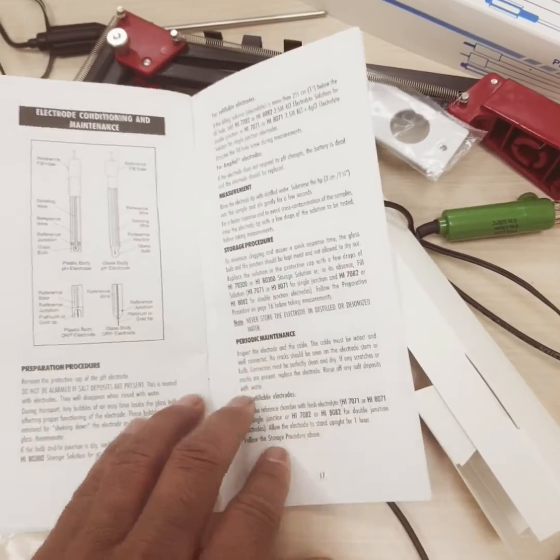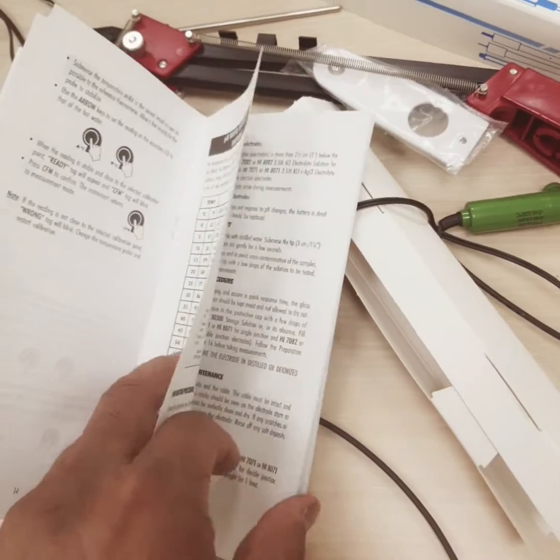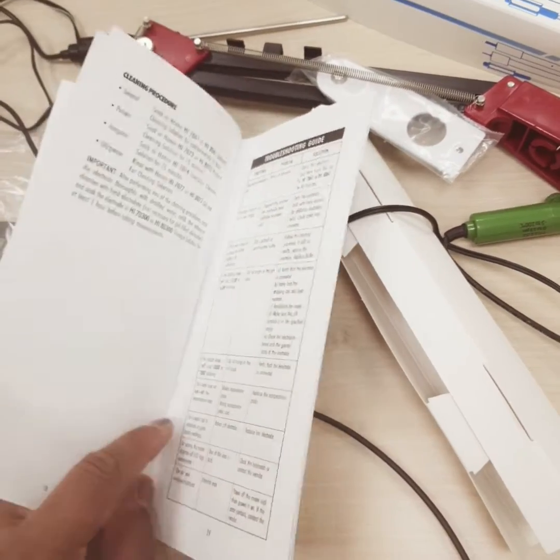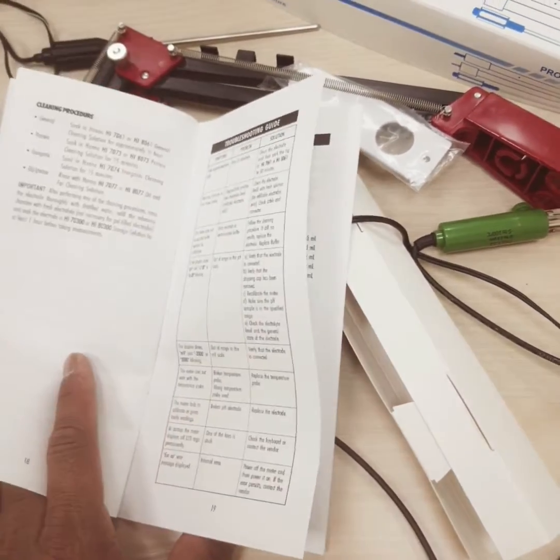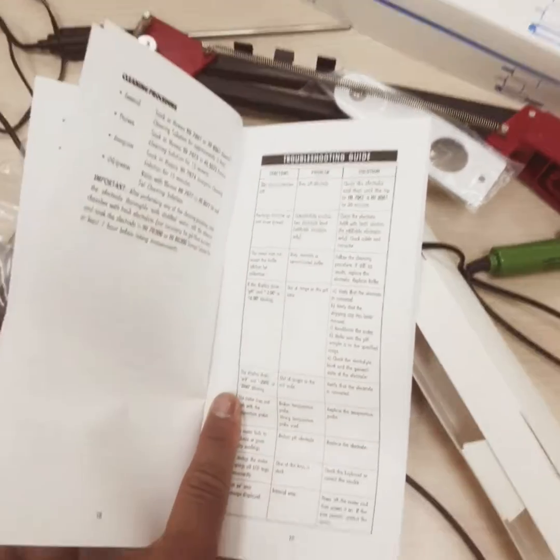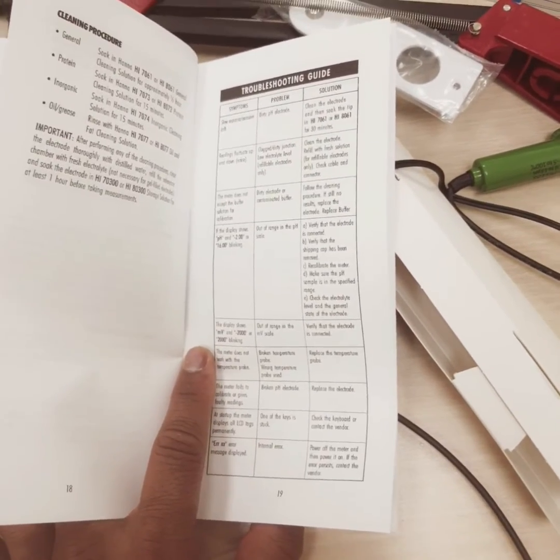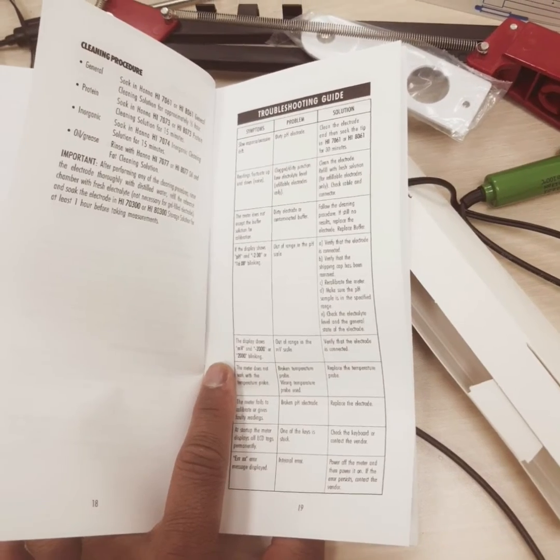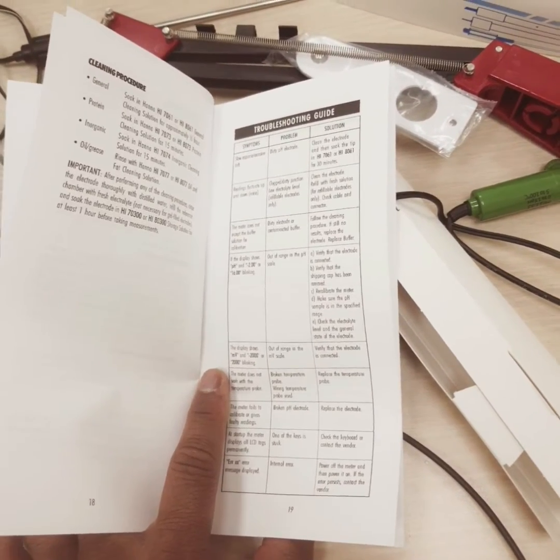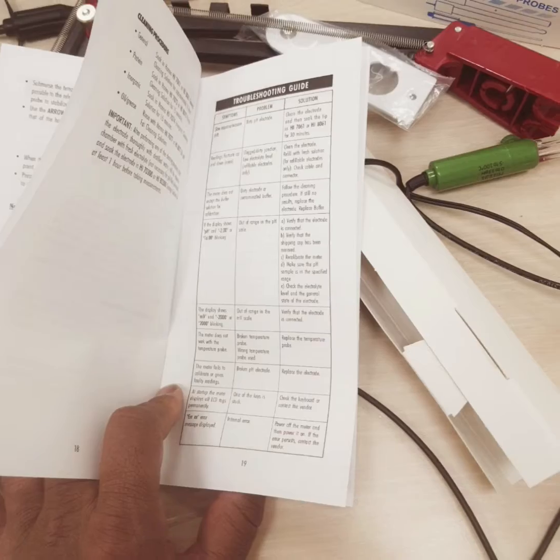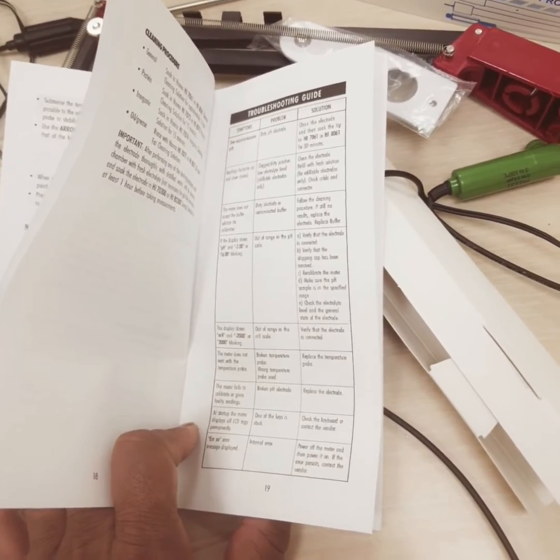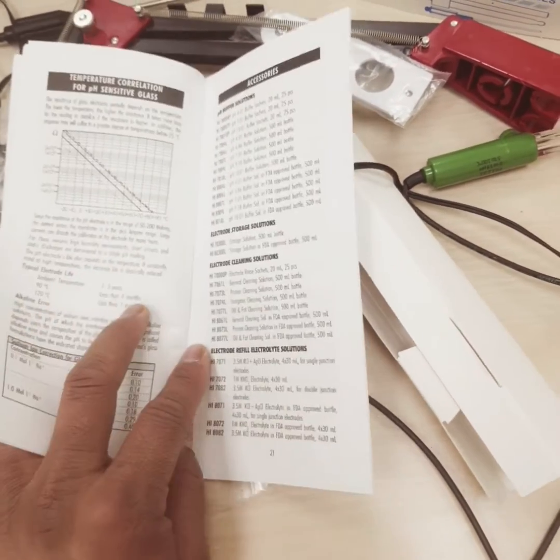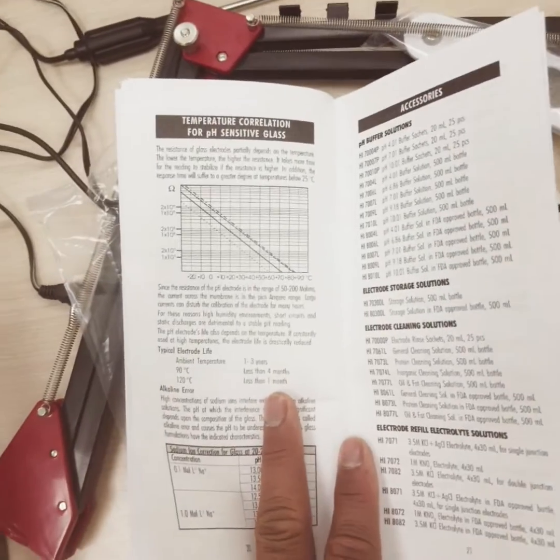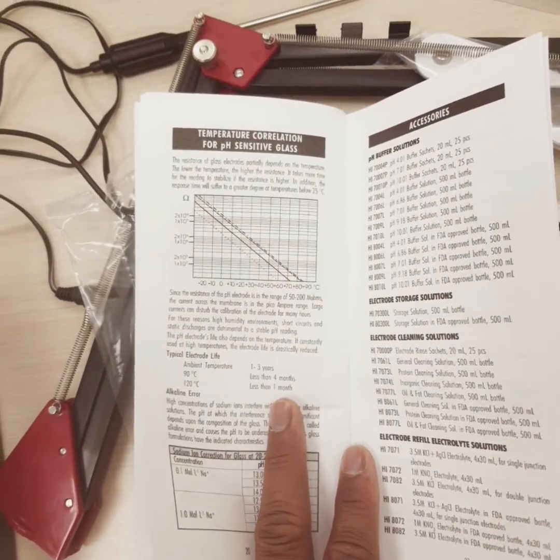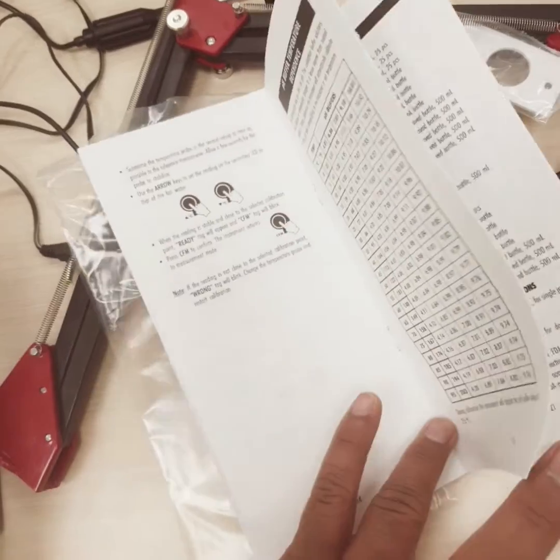Now there are certain more procedures, the periodic maintenance, the storage procedure, how we have to store the electrodes, and these are the troubleshooting guides if the response is slow or there is an excessive drift in the pH value, it's drifting a lot. Okay, and also if you are trying to calibrate and the electrode is not getting calibrated, and these are some more graphs. Okay, temperature correlation for pH sensitive glass. Now let's start the calibration part.